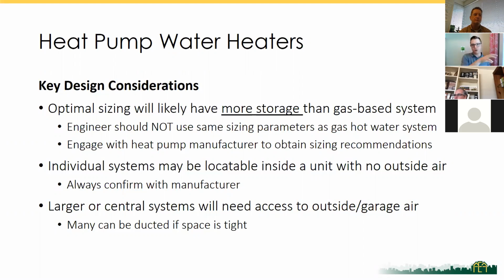With heat pumps, we actually want to do it the other way. The engineer should not size the system using the same parameters as for a gas water heating system, or you'll end up with a heat pump water heating system that's very expensive to both purchase and operate. An efficient heat pump water heating system will have a lot of storage and a relatively small heat pump.